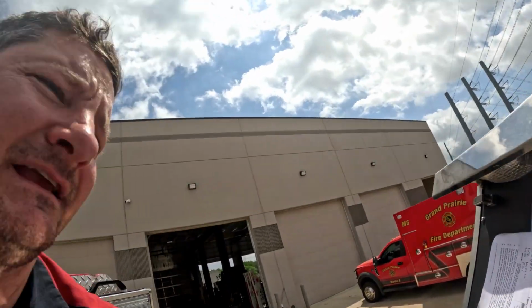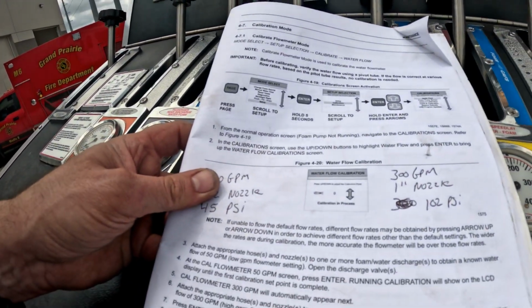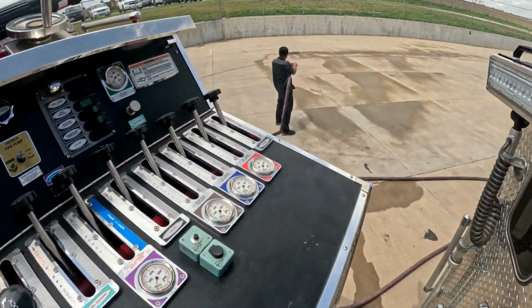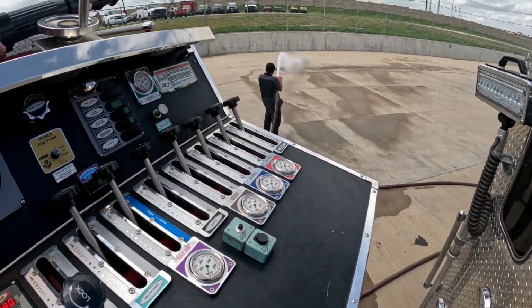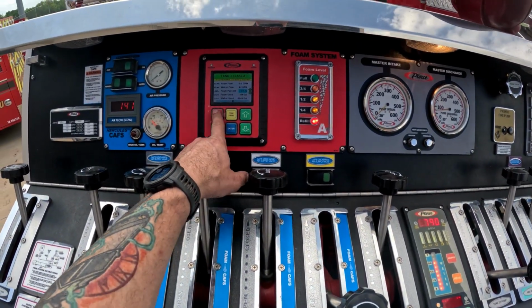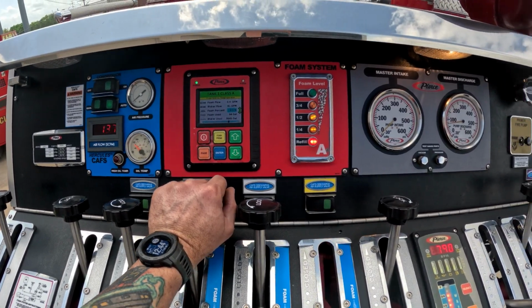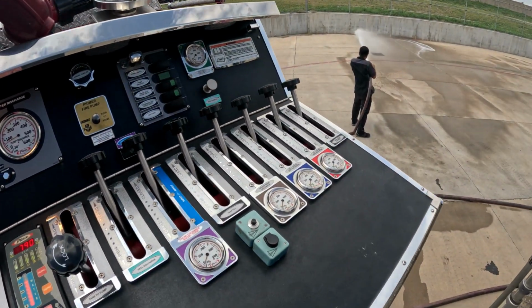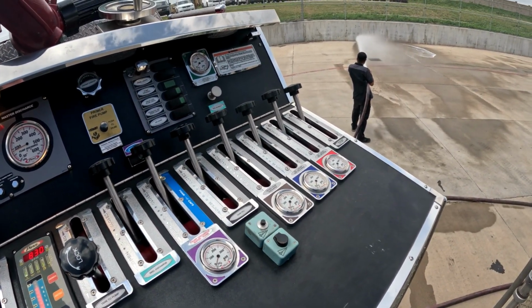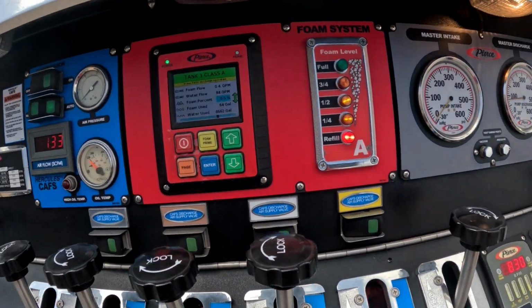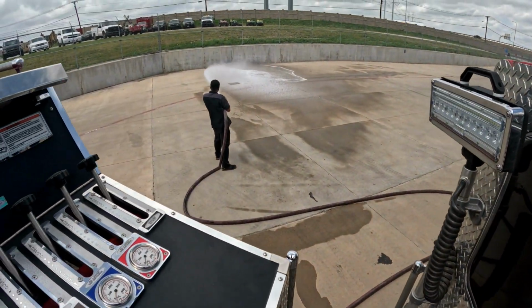So now the flow meter correlates and corresponds with the foam pump on your LVDT transducer. So that's a critical portion that needs to be set correctly to these numbers for you to get the proper percentage of foam out. Pull a line and we'll start flowing foam, see what we get. All right, we got our line charged by Sammy down there. All right, go ahead and open it, Sammy. We're gonna turn our foam on. We're at 0.5% right now. Sounds like we got foam coming. Yeah, he's got some foam coming.